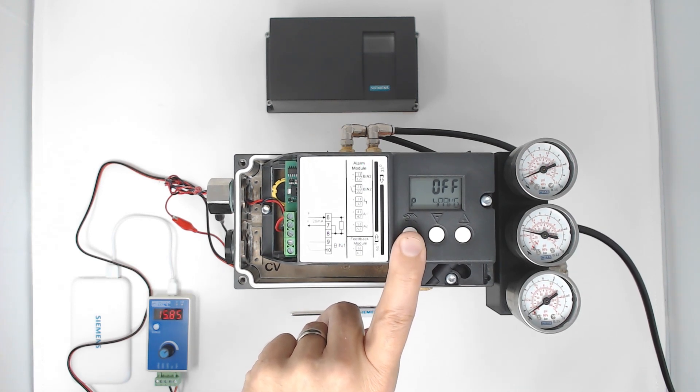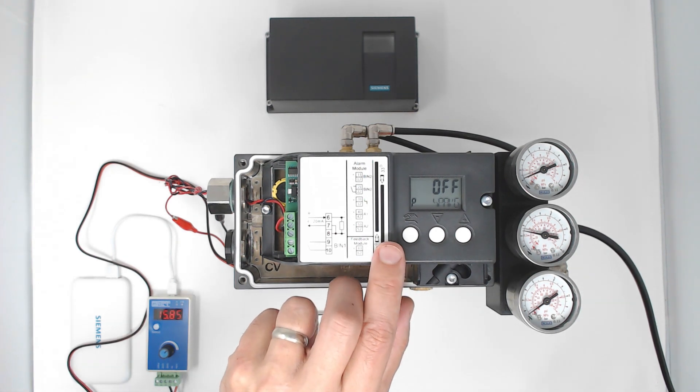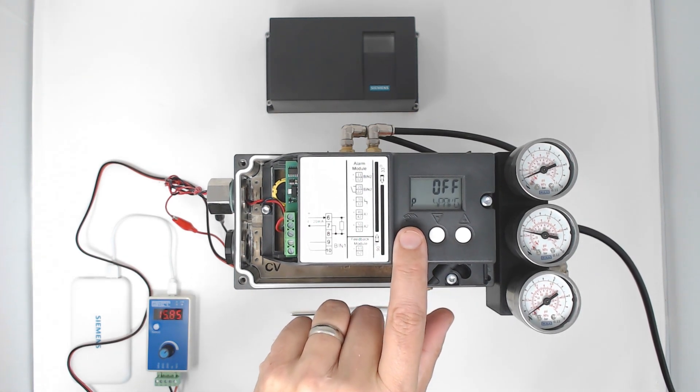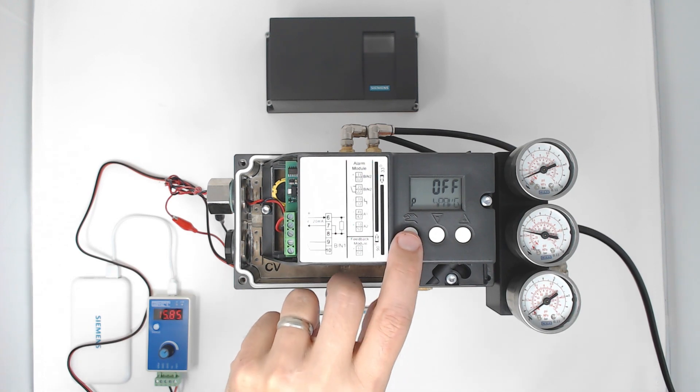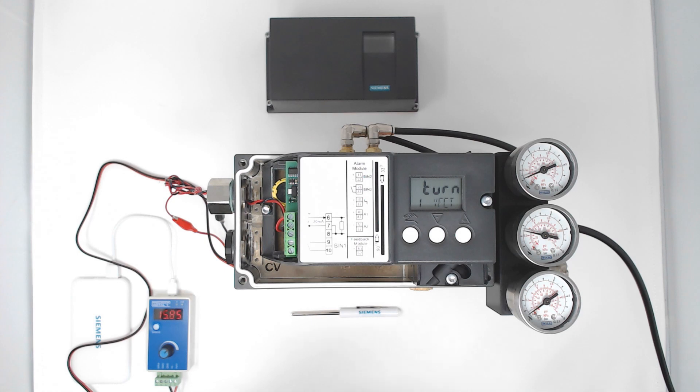Position average is a diagnostic that is detecting the entire process loop, not just the valve assembly itself, because it records its position average based on a time base that you provide. If for some reason upstream or downstream from the process valve is causing the positioner to control that process in a different location off its average, it can indicate that to you.